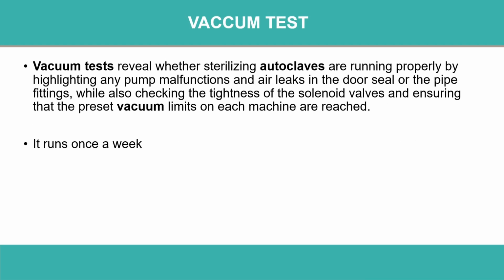Actually, these are the vacuum test or warm and leak test. It is written that it runs once a week because here there are very few cases. So it is written once a week, but in a big hospital, it runs daily. The name is written as vacuum test, but mostly it is written as warm and leak test. In some autoclaves it is written only as leak test. So it is mandatory to check first. First we run this test without putting anything inside.